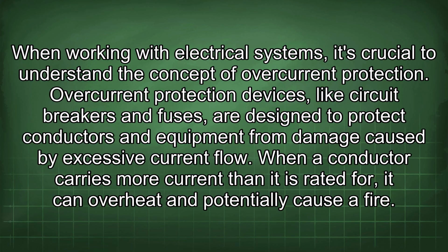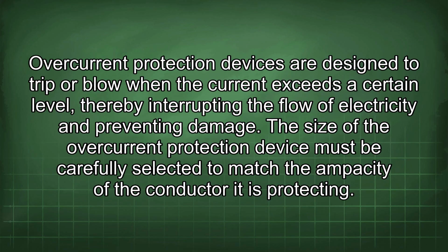When a conductor carries more current than it is rated for, it can overheat and potentially cause a fire. Overcurrent protection devices are designed to trip or blow when the current exceeds a certain level, thereby interrupting the flow of electricity and preventing damage.